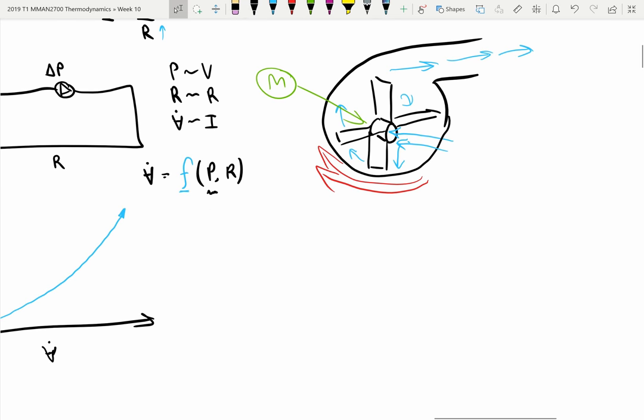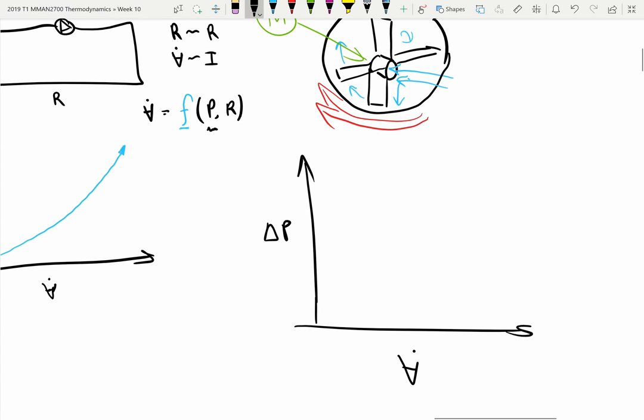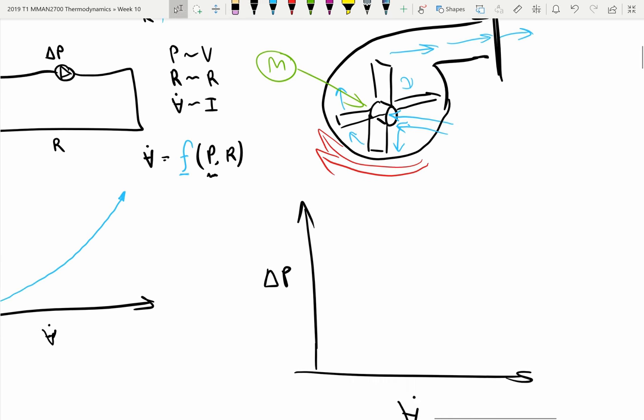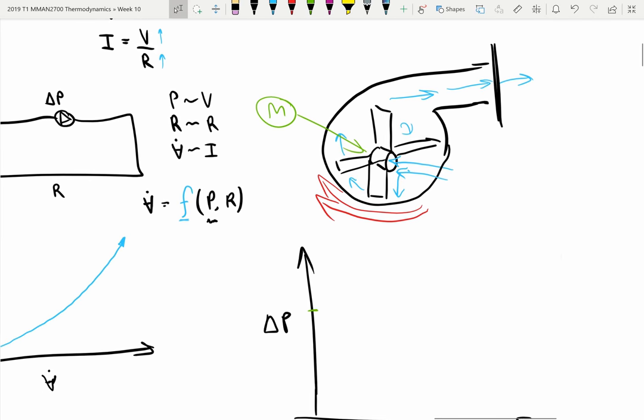Let's think about the performance curve for this pump — we call this a pump curve. We're going to have some ΔP and some volumetric flow rate. If we deadhead the pump — so if we just have a blanking flange across this pipe and don't allow any flow out of the pump at all — there'll be some pressure the pump can produce at zero volumetric flow rate. That's the highest pump pressure the pump will be able to produce.